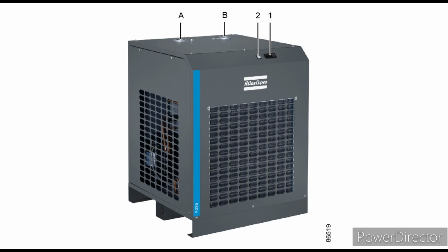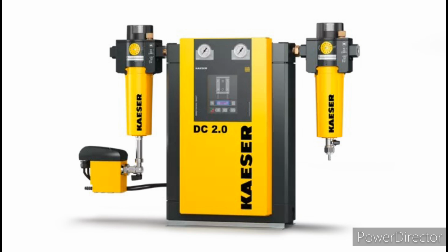Non-cycling refrigerated air dryers are also available, and variable speed refrigerated air dryers as well. The advantages of refrigerated air dryers are low initial capital cost, relatively low operating cost, and low maintenance cost. For these three reasons, customers like to install refrigerated air dryers. There are many brands of dryers in the market, such as Atlas Copco, CP and Kaeser. There are a lot of air dryer manufacturers.